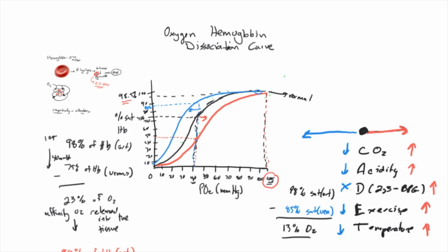You put a pulse oximeter on a patient's finger, and it will still read 98.5%, although with extreme cold, sometimes when we get vasoconstriction to our digits and our extremities, it will not give an accurate reading anyways, but let's assume that we're getting an accurate reading. This gives the illusion that the body is oxygenating adequately enough. But in reality, we're only giving 13% or less to the tissues, and the tissues can become hypoxic.